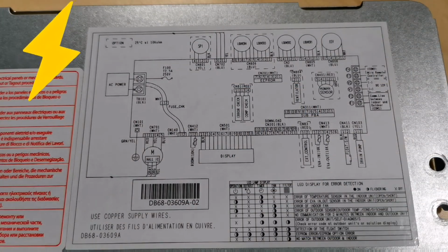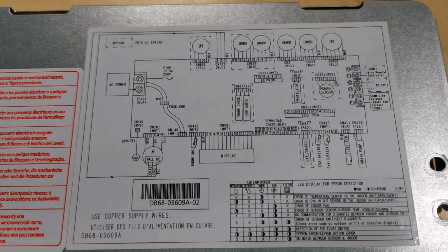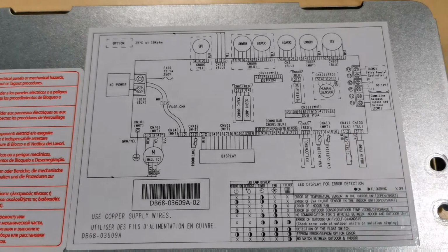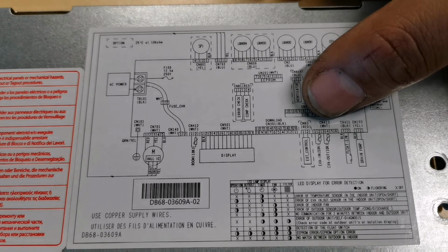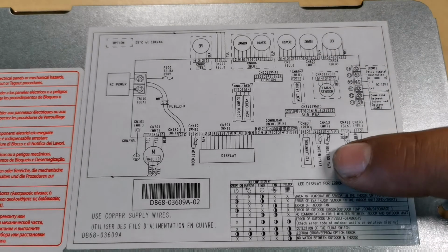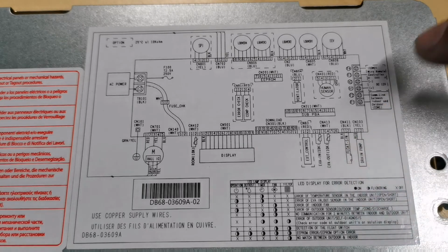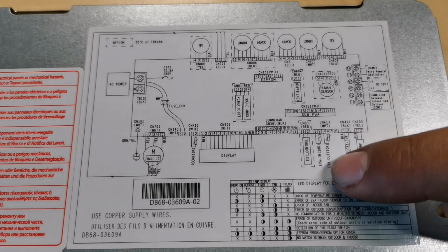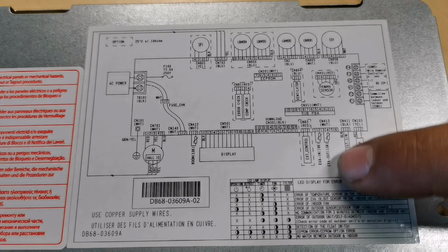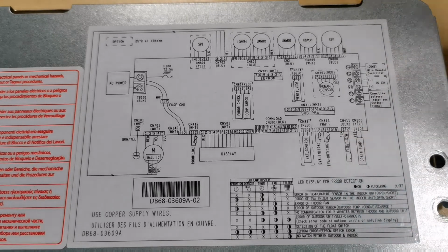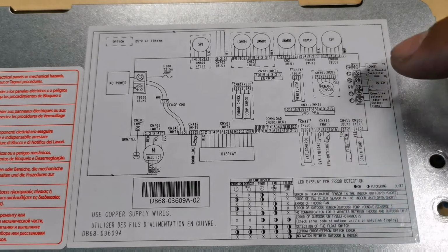Alright, so let's have a look at the circuit diagram here of the Indoor unit, and we can see right there connector CN413, that our EVA in and EVA out is connected there, and that says it's a 10K resistor or sensor, which is effectively just a resistor.